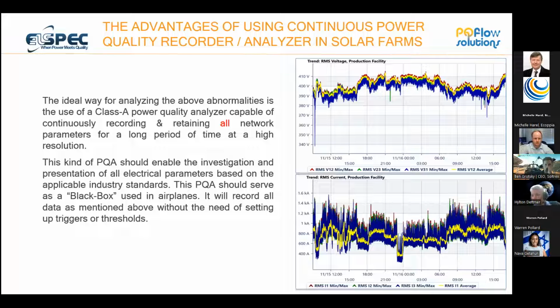So what the Elspec black box range actually does for us is store the sine wave in high resolution - 256, 512, 1024 samples per cycle. We store the voltage and current for the full period of time. I've got clients that we've had on our cloud server for 3 or 4 years, and I can go back 3 or 4 years and show you every single network waveform from a voltage and current perspective because of the Elspec technology.